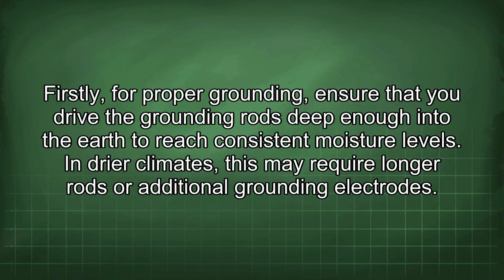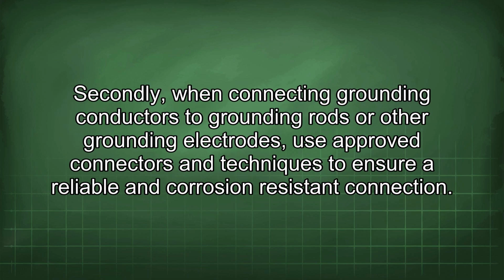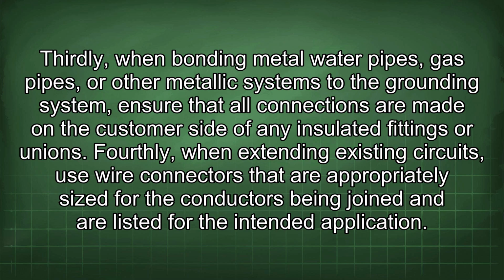others. Firstly, for proper grounding, ensure that you drive the grounding rods deep enough into the earth to reach consistent moisture levels. In drier climates, this may require longer rods or additional grounding electrodes. Secondly, when connecting grounding conductors to grounding rods or other grounding electrodes, use approved connectors and techniques to ensure a reliable and corrosion-resistant connection. Thirdly, when bonding metal water pipes, gas pipes, or other metallic systems to the grounding system, ensure that all connections are made on the customer side of any insulated fittings or unions.